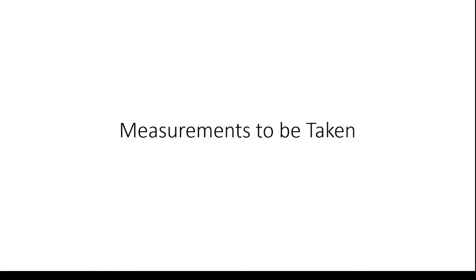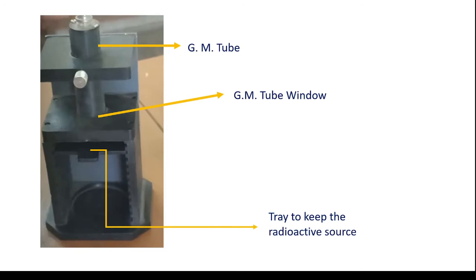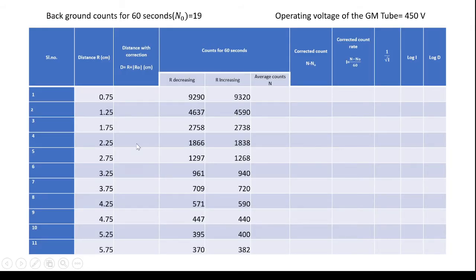Now the measurements to be taken. One of the important measurement which you have to do is basically the R which is going to be called as the distance. This I am taking from this point up to the top of the radioactive source. And this R value is kept on changing by keeping the tray at various slots. The slots you can see it here. This is the data which I have collected where R is the distance to various slots which are shown here and the corresponding counts as R increases and R decreases are shown here.